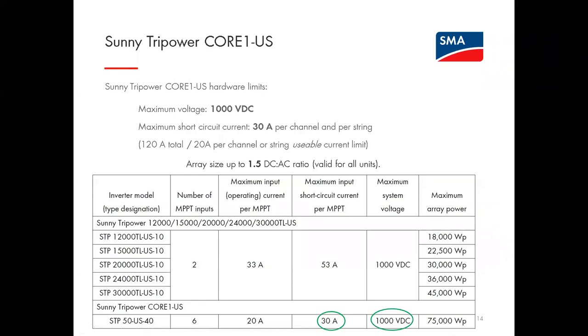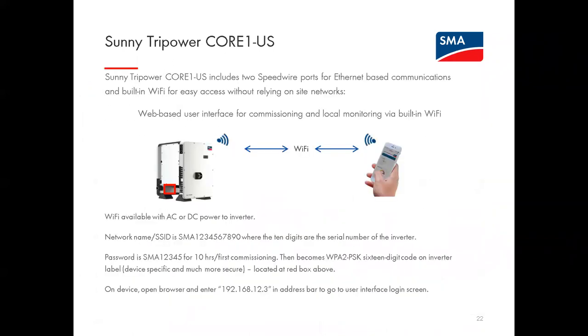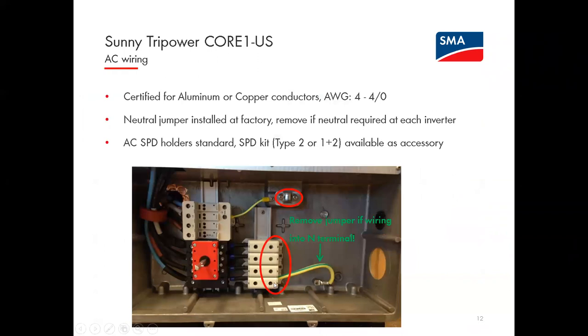Okay. So moving on, Emil, this may have been answered. I believe you're asking how to argue to get rid of the question we were talking about earlier with the AHJ. I'm guessing that question was answered. Let me know, Neil, if not. Generally this is probably related to the neutral, and again, that is really an AHJ decision. We can provide documentation that the neutral is only used as a sensing mechanism, that there's no current put out on it. So we can provide some level of technical explanation of why the neutral conductor does not need to be going back to the transformer, but at the end of the day, it would be the final decision of the AHJ whether or not they would require it. Okay.